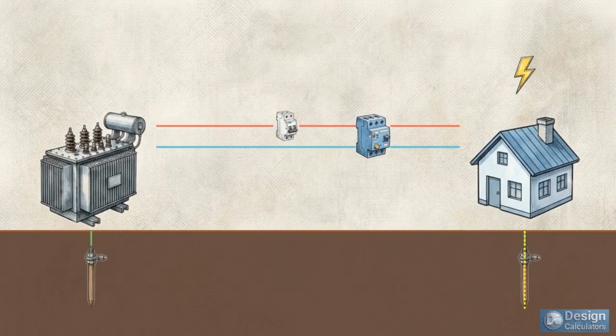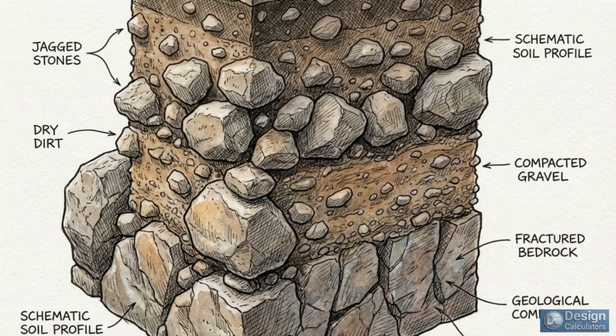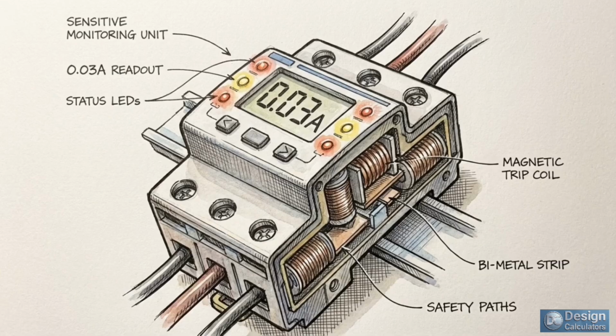To survive this weak current, the TT system requires a residual current device, or RCD. Rather than waiting for a massive power surge, the RCD monitors the circuit for tiny electrical leakages into the soil. The moment it detects a drop, it instantly severs the connection. By prioritizing physical independence from the grid, the TT system gives up raw stopping power. It relies entirely on hypersensitive monitors to catch a fault before a human does.